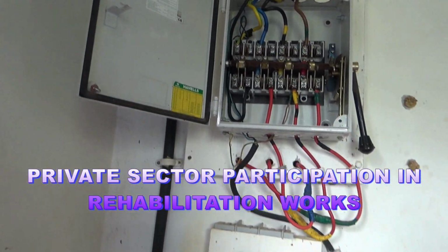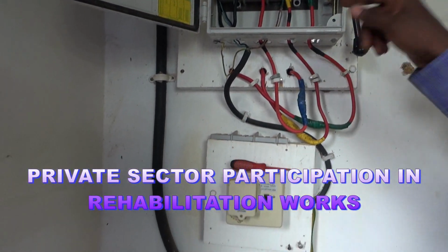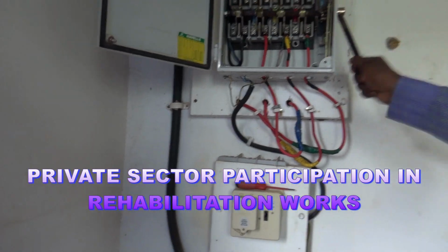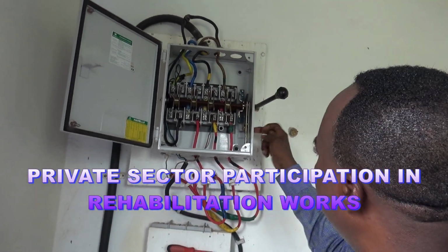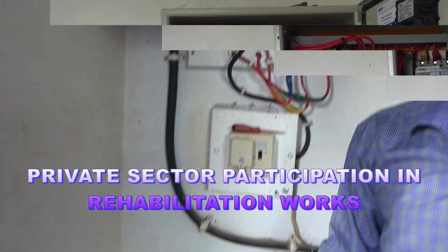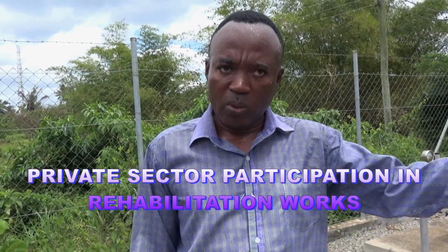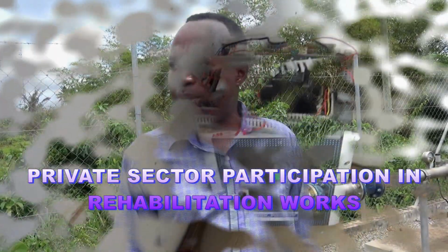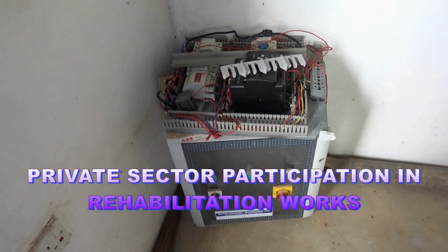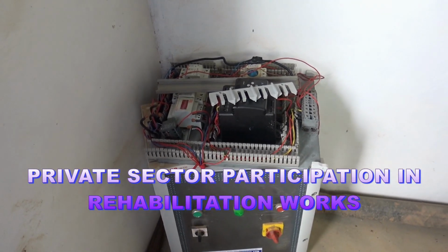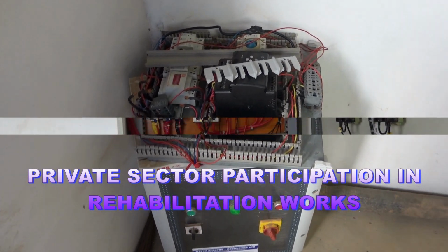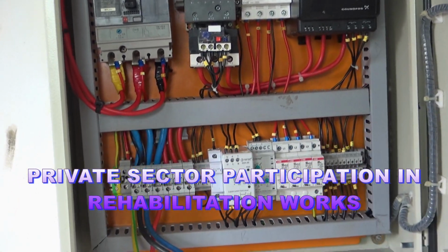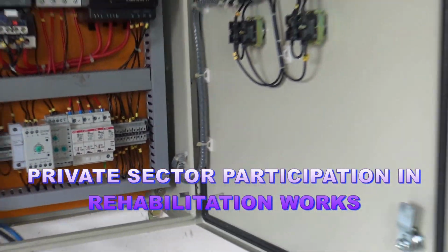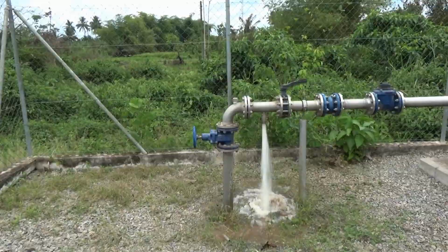So when we came, we inspected the system, and then we found out that the main switch, which was supplying power to the control panel, was having sparks, and so it was able to cause damage to the old panel. And we recommended that the panel was beyond repairs. So now what we have done is that we have brought a new panel, and we have just fixed the pump and getting water out.